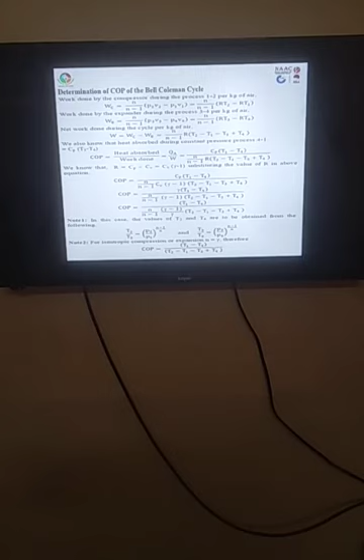The COP is calculated as heat absorbed upon work done, heat absorbed or heat removed from the low temperature. So it is equal to Cp into (T1 minus T4) divided by n upon n minus 1, then multiplied by R, and then (T2 minus T1 minus T3 plus T4). If we substitute the value of gas constant R equal to Cp minus Cv, which equals Cv into (gamma minus 1), then the final equation for COP we obtain as, in the numerator T1 minus T4, divided by n upon n minus 1 multiplied by (gamma minus 1) divided by gamma, then multiplied by (T2 minus T1 minus T3 plus T4).